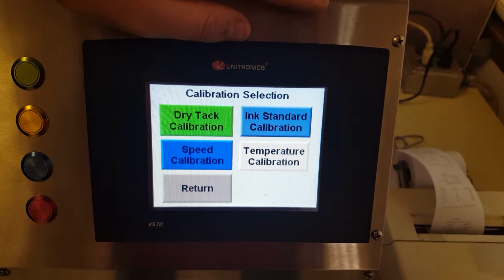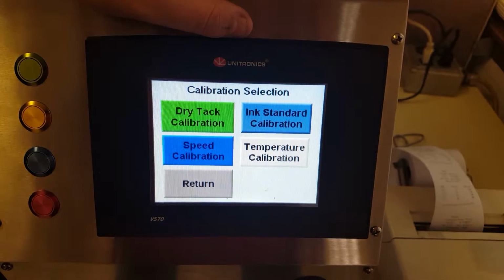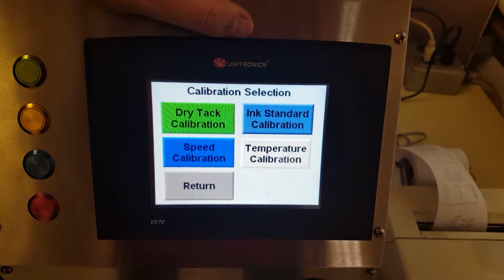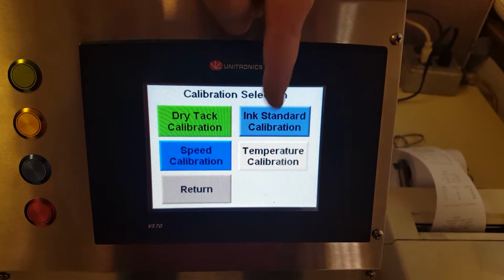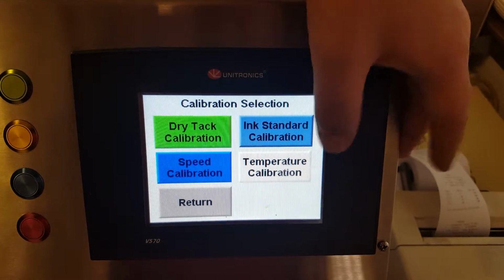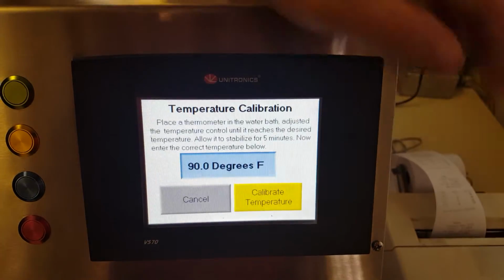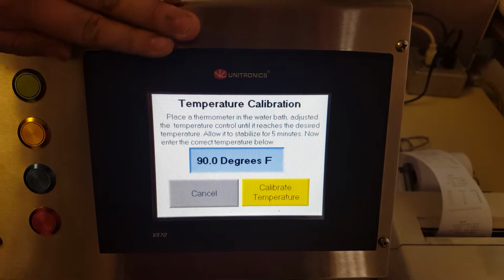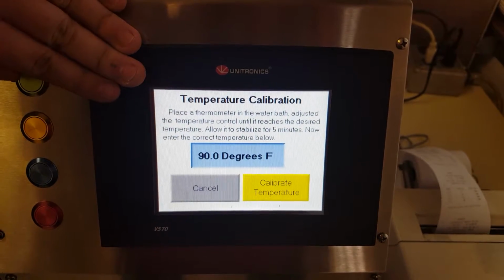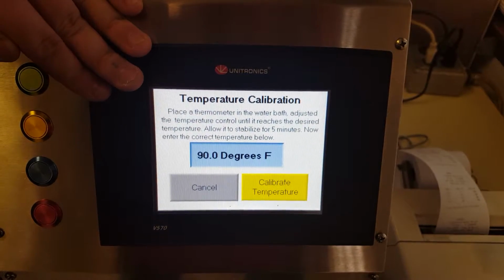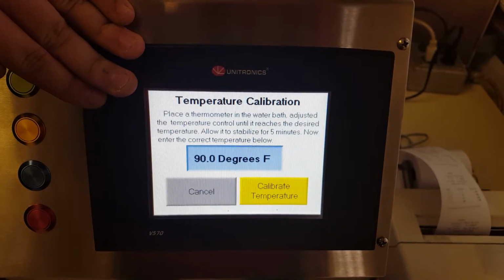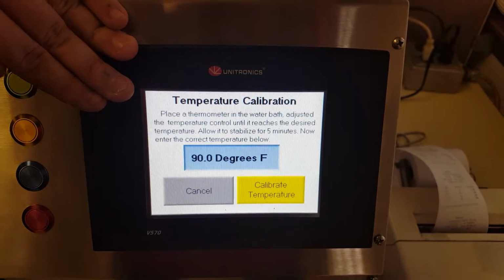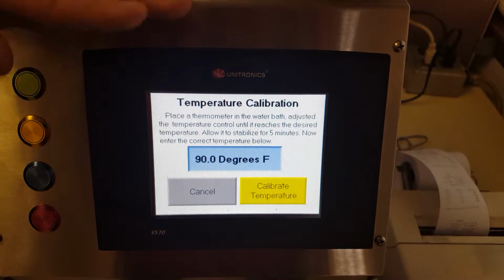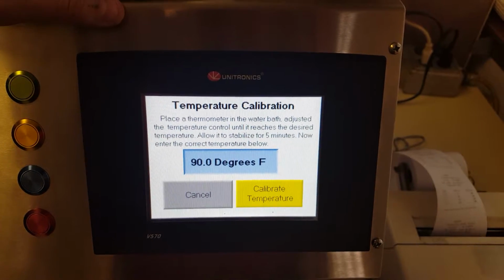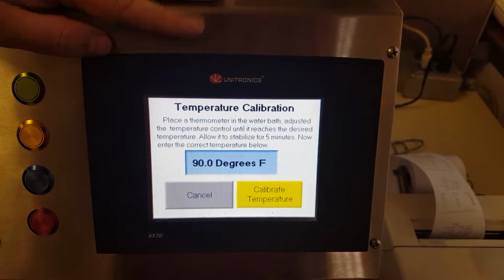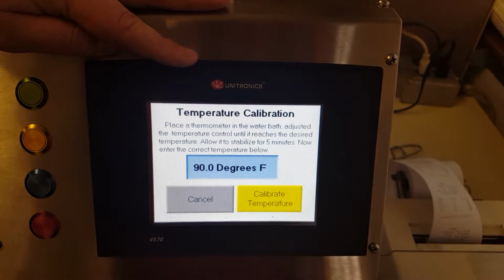I'm going to begin with the bottom two, simply because they're the easiest and they're very straightforward. The first one I'm going to begin with is our temperature calibration here, and when we click on this button, it brings us to a screen that gives us a portion of text. Every screen in the calibration mode will give you about a paragraph to explain exactly what you're doing and why you're doing it, and will walk you through step by step to make it as simple for the operator as possible, meaning that anyone can more or less calibrate this by themselves if they follow the instructions here.